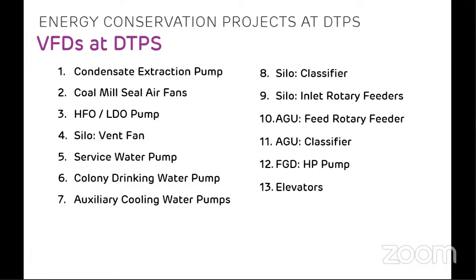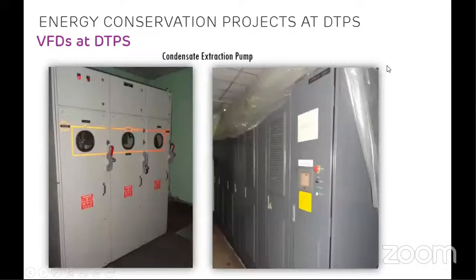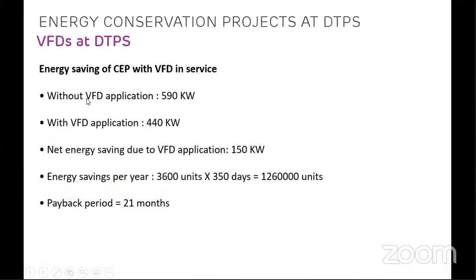In the lecture about VFDs, my colleague will give you detail about each VFD and how it functions. I'll just explain how much energy is saved. This is our condensate extraction pump VFD. It is a high voltage motor, 6.6 kilovolt. And this is the variable frequency drive panel, which runs the motor at variable speed by varying the motor's frequency. Without the VFD, the consumption of the motor was 590 kilowatt, or you can say 600 kilowatt. Once we installed the VFD, we reduced the motor speed to 90, sorry, 80%. So the kilowatt rating was reduced to 440 kilowatt. The energy saving due to this was 150 kilowatt.